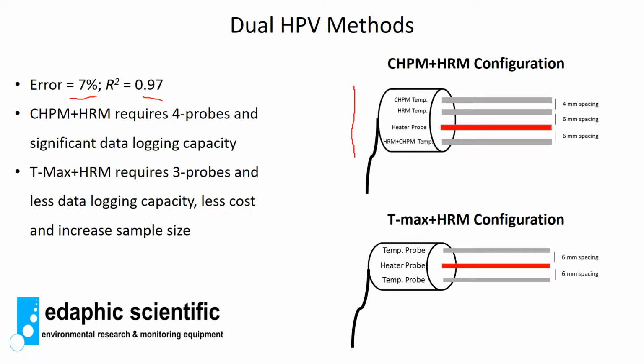It was a 4-probe configuration, and you can imagine that it looks a little bit messy in this graph here, and in practice when you're out in the field, using a 4-probe configuration might be a little tricky. You can run into some installation errors with probe misalignment. There's also more wounding that you're inflicting on your plant, and not only that, but there's more temperature sensors that you need to measure, so you need to have more data logging capacity.